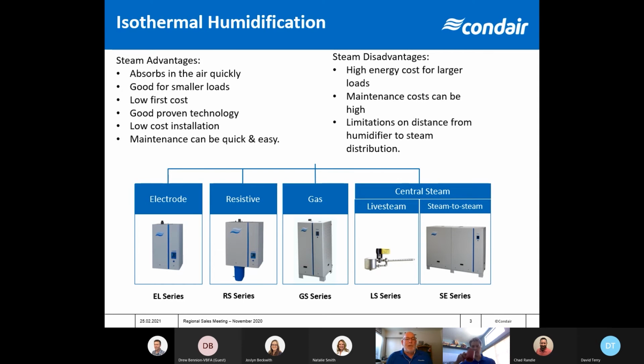So down at the bottom of this slide, we list all of our steam humidifiers. So we have our EL series, that's the electrode steam you're probably familiar with. These have the disposable plastic cylinders that we boil the water. The great thing about these, very quick, easy maintenance. 5 to 10 minutes, swap out the cylinder, it's back in business like a brand new humidifier again. But these can only use regular potable water, cannot use RO or DI water.